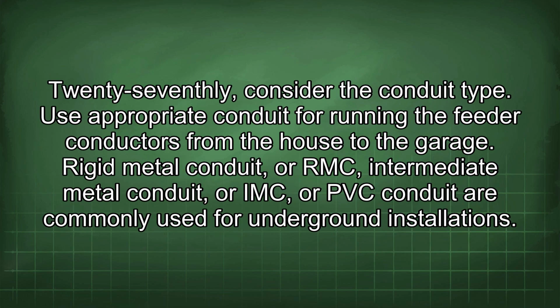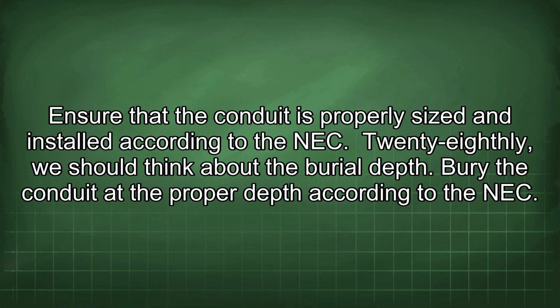27thly, consider the conduit type. Use appropriate conduit for running the feeder conductors from the house to the garage. Rigid metal conduit, or RMC, intermediate metal conduit, or IMC, or PVC conduit are commonly used for underground installations. Ensure that the conduit is properly sized and installed according to the NEC.